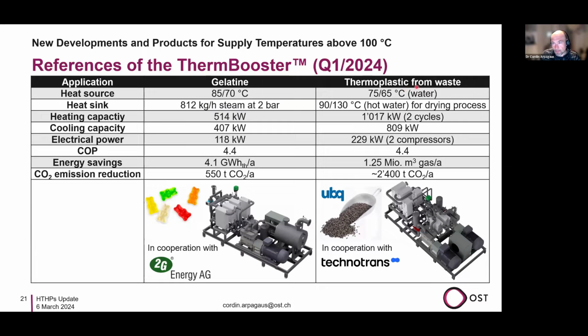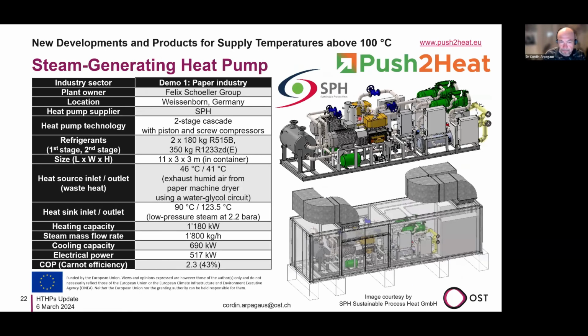And here another one, thermoplastic from waste as an application. Here the application is a drying process. The system is double the size, or like 2 cycles on one rig. So they achieve 809 kilowatt nominal cooling power and 1017 heating capacity. And this is a system they have for our Push to Heat project, which is a European funded project where our university OST is also participating as a Swiss university. We are still allowed to participate in European projects, and that's the heat pump that will go into a paper factory from the Felix Schoeller Group.